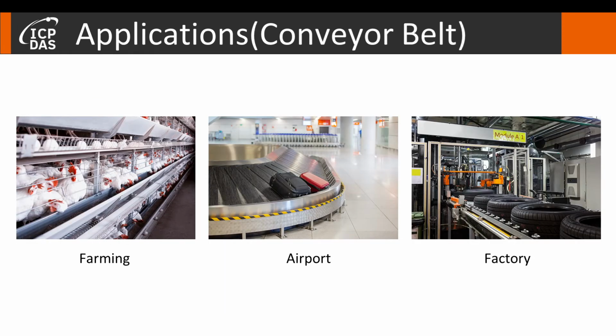For example, RPAC 2650AM is applied to most conveyor belts because they always operate 24/7 in farms, airports, or factories. As we mentioned before, there are triple Ethernet ports. So, when the main RPAC doesn't work or there is an electrical breakdown, the main RPAC can switch rapidly to the other backup RPAC so that the whole system does not shut down, which would make the cost go up. So the application's design is more convenient and more practical. So I believe this is a necessary product for you.